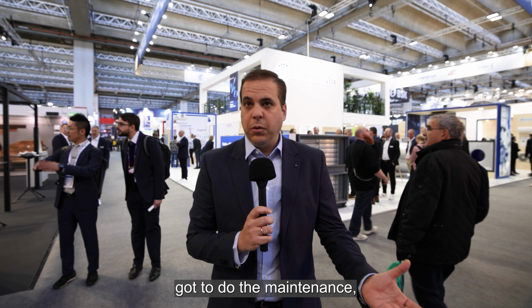There are some key factors that should be decided beforehand, like building levels of occupancy, because this affects how the system is designed. It's also important to know the climate and humidity levels, since not every region should have the same type of system. What type of energy efficiency are we looking for? Heat exchanger, energy recovery? Filtration capabilities are also important, since pollution can affect a lot. Of course, we need to comply with building regulations, which are getting stricter every time, so we need to fulfill the law. And maintenance requirements must be considered as part of the design.